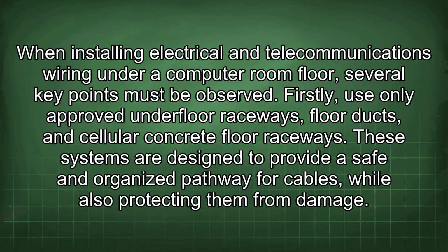When installing electrical and telecommunications wiring under a computer room floor, several key points must be observed. Firstly, use only approved underfloor raceways, floor ducts, and cellular concrete floor raceways. These systems are designed to provide a safe and organized pathway for cables, while also protecting them from damage.